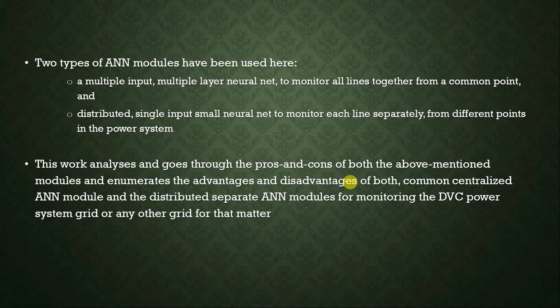To generate the training data for a given loading condition based on day-ahead load forecast, unit commitment, and scheduling, a load flow program is run to calculate loading conditions of the transmission lines. After the line loadings are calculated, it is given a differential calculative error margin of plus minus 10% to generate the appropriate amount of training data for the ANNs that will be used for monitoring the lines of the network.